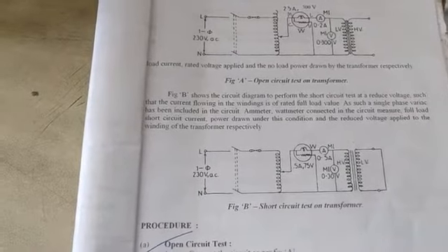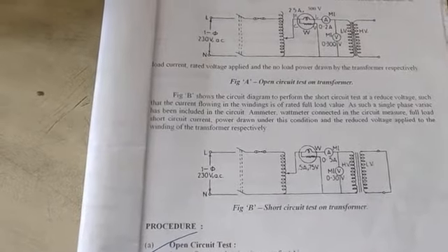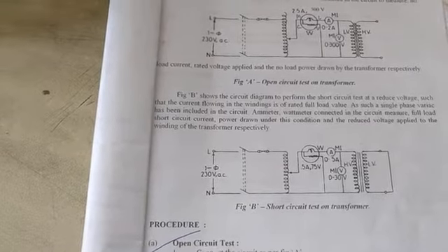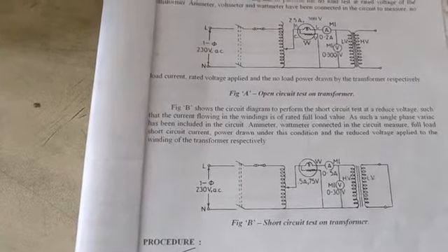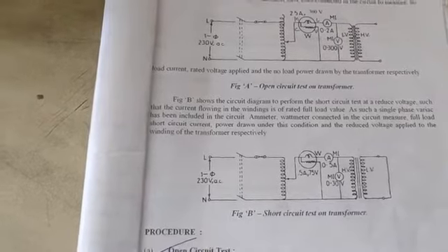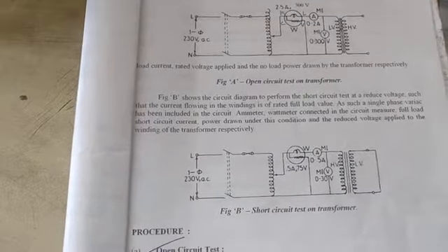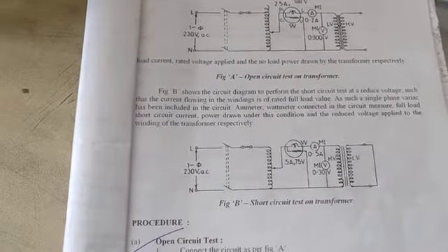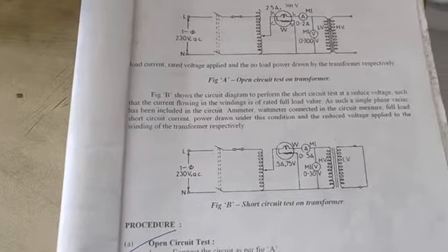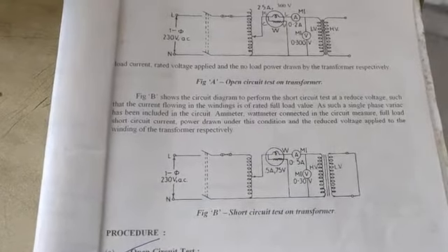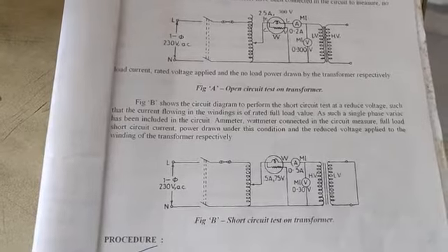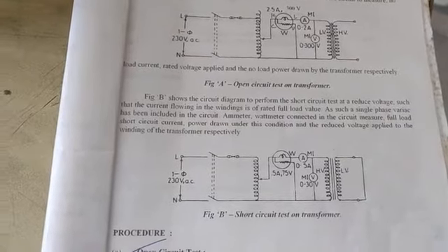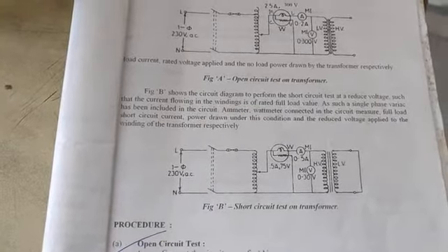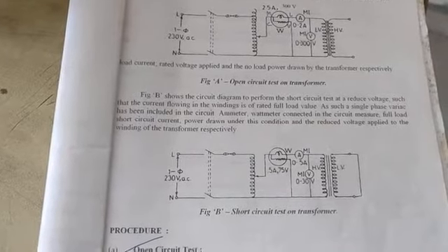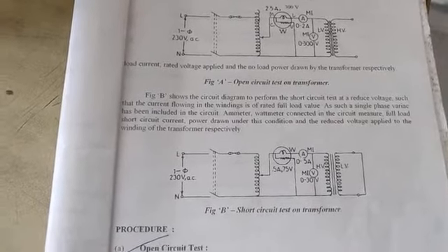because secondary is short circuit, and if you increase the level of voltage, an excess amount of heating is produced in the winding. So if you perform this test for high level of voltage, the winding of transformer gets damaged. So in order to protect the transformer, the important point is this test is performed on the low level of voltage.